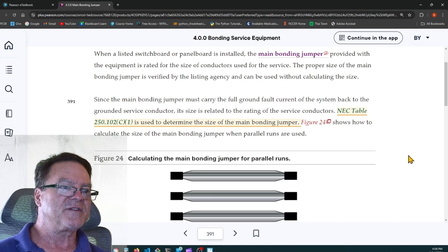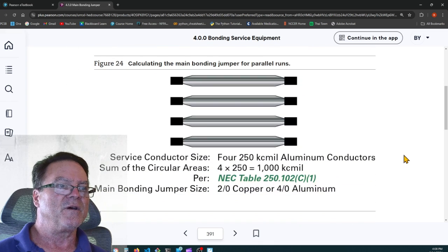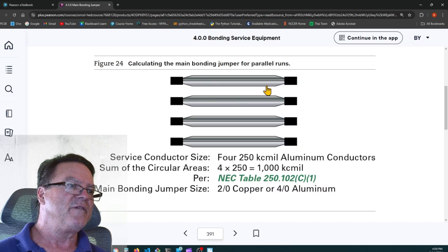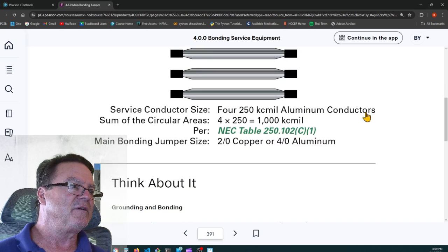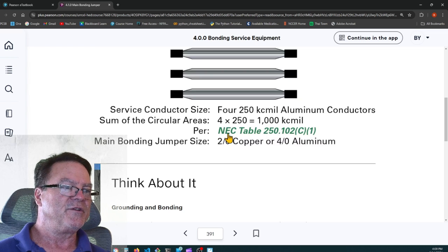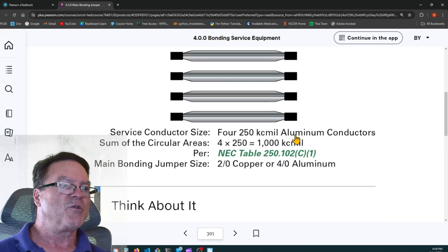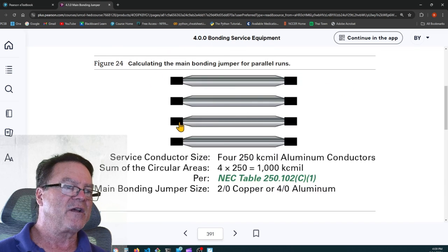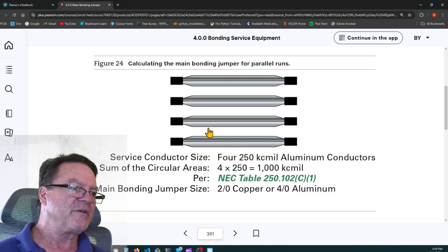Figure 24 shows how to calculate the size of the main bonding jumper when parallel runs are used. So, calculating the main bonding jumper for parallel runs. You've got parallel runs. You're going to take 4 250 kcmil aluminum conductors. That is a total of 1,000 kcmil. So you use table 250.102C1, you go down to 1,000 kcmil, and you find it's a number 2-aught copper or 4-aught aluminum. So each one of these parallel runs has to have a 2-aught copper in it. Each equipment grounding conductor in this conduit has to be able to carry the total fault current, not just the fault current of this parallel run, but the total fault current of the entire system. So you have to size it according to the 1,000 kcmil, and then that's the size of the bonding jumper that you use inside these raceways.